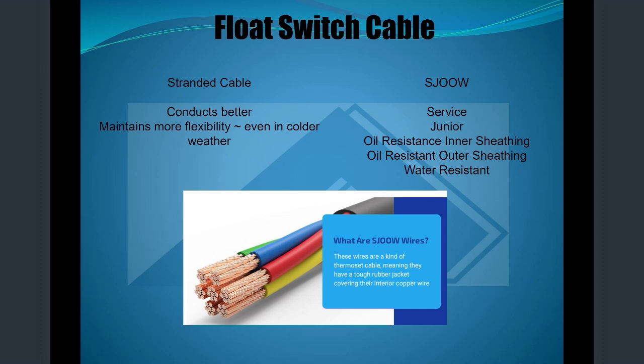And then inside the little cable here are strands of wire. The strands that we have, I think ours are like 168, 162 strands. The more strands you have, the more flexible the cable is, which is great for when it's cold outside, because cables get pretty stiff. So that just talks about the cable standards. It conducts better and maintains more flexibility even in colder weather. The S stands for service, J is junior, the first O is oil resistant inner sheathing, the second O is oil resistant outer sheathing, and the W is water resistant as well. It's a kind of thermoset cable, meaning it has a tough rubber jacket covering its interior copper wires.